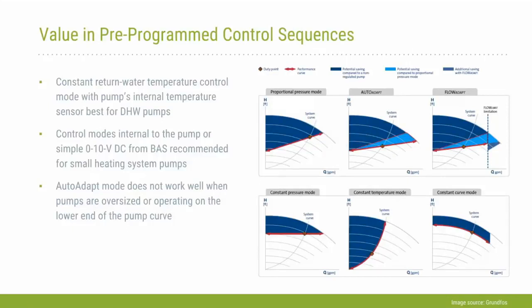So one of the main benefits for these pumps is they do have pre-programmed control modes that are built into them. The constant return water temperature is a nice feature where essentially you're only using the on-off from the building automation system control. We ended up using just a 0 to 10 volt control for the heating pump. The reason for that was the auto adapt mode does not work well if the pump is oversized and operating on the lower end of its pump curve. But again, you can use the internal control mode of the pump.